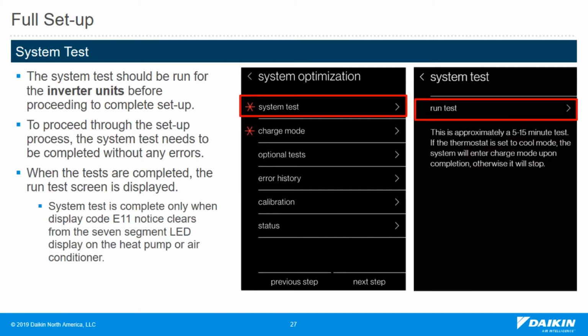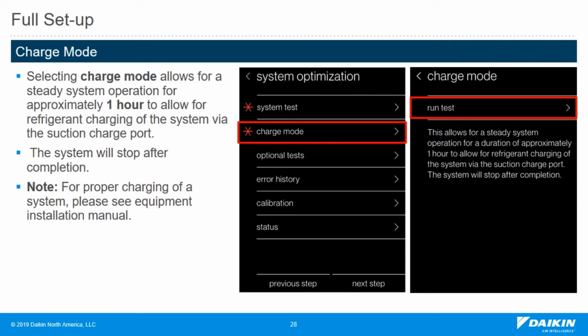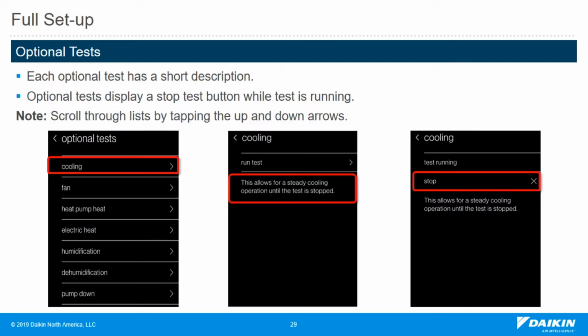When you do the run test, it'll take 5 to 15 minutes. When the thermostat is done, the E11 code will go away from the outdoor unit and the thermostat will return to this mode. Again, the charge mode allows 1 hour. The refrigerant charging system via the suction port outside, and it will stop after completion. Optional tests. We have a list of optional tests. If you have a 2-speed unit, here's where you can go test your cooling and hit run test. This is not for inverters. This is only for the 2-speed unit or a 1-speed outdoor unit.